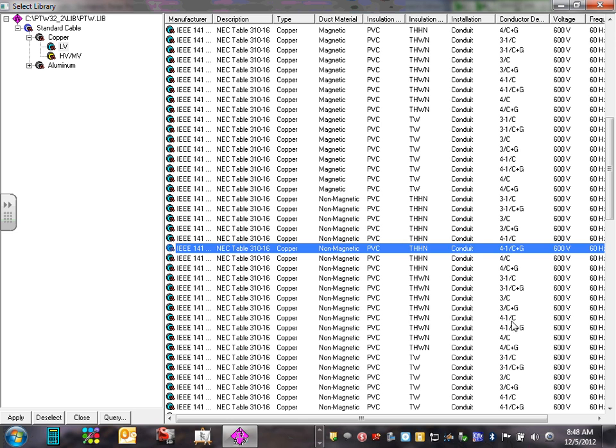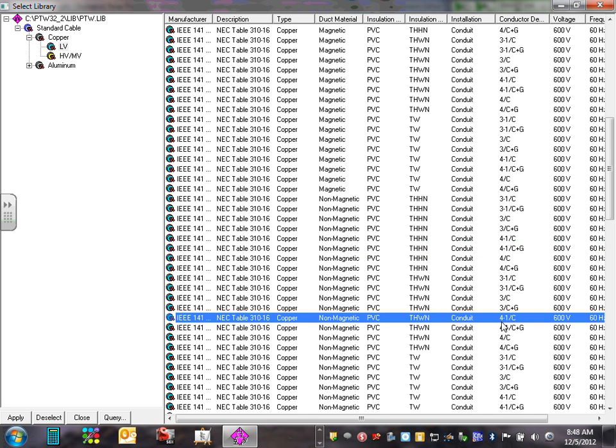Okay, so here's what I would like you guys to focus on, not this one, Chad. Right in this one. And I'm going to tell you why this one. Look at this. This is 310-16. They didn't change it after she got married and changed her name to 310.15(B)(16), right? That's the one that you use. We're using copper because we're engineers. We kick butts. We don't care about aluminum.